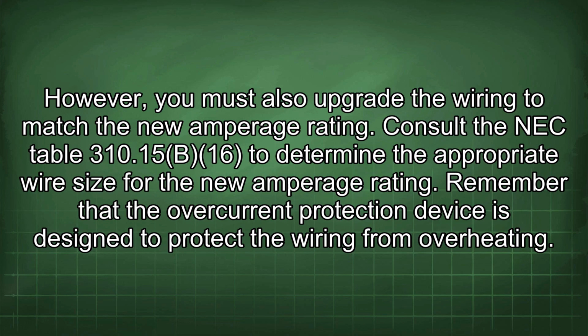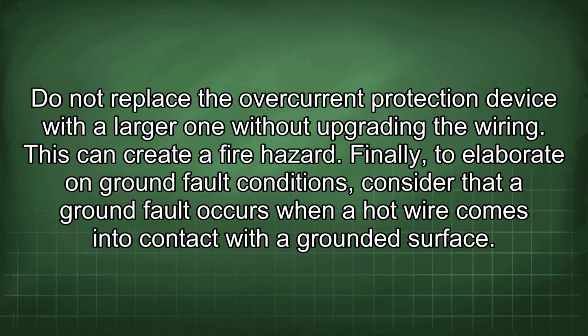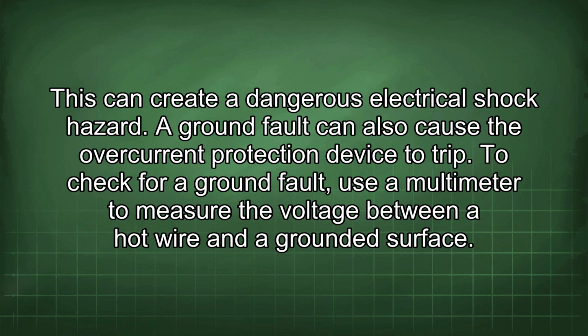Remember that the overcurrent protection device is designed to protect the wiring from overheating. Do not replace the overcurrent protection device with a larger one without upgrading the wiring. This can create a fire hazard. Finally, to elaborate on ground fault conditions, consider that a ground fault occurs when a hot wire comes into contact with a grounded surface. This can create a dangerous electrical shock hazard. A ground fault can also cause the overcurrent protection device to trip.